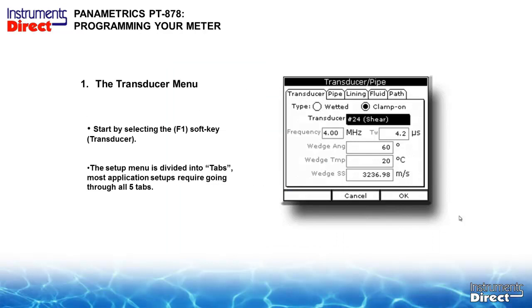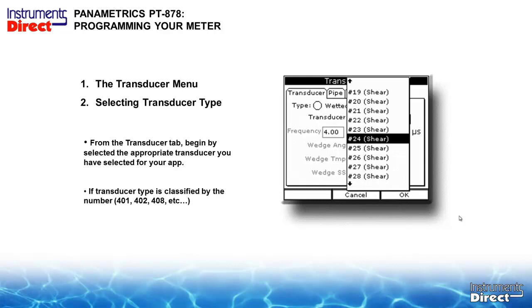So now we're going to go to the transducer menu. We select the F1 soft key for transducers. And this is what you're going to have to do each time you change your hardware. From here, it's divided up into a bunch of different tabs. In this case, we've selected a clamp-on transducer. The transducer menu has a host of drop-down screens for selecting your type of transducer.